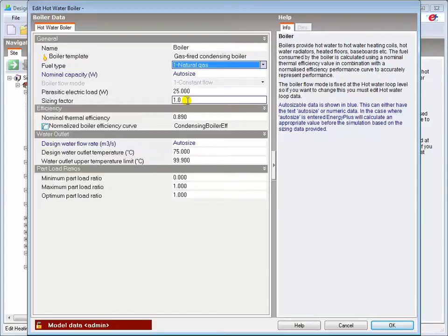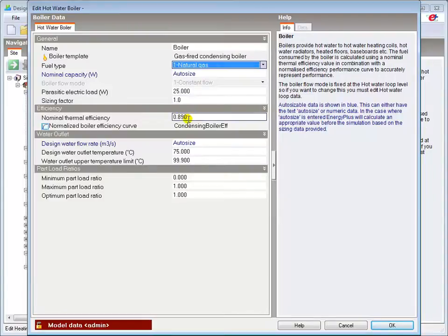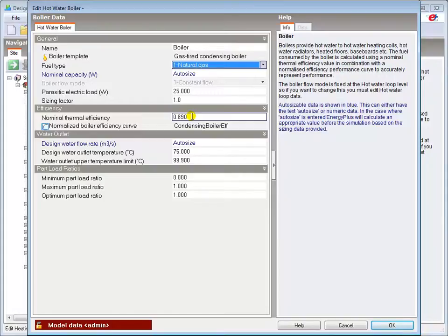The nominal thermal efficiency is the manufacturer's efficiency at rated output conditions, i.e. when operating at 100% capacity and using the fuel's higher heating value, also called higher or gross calorific value.